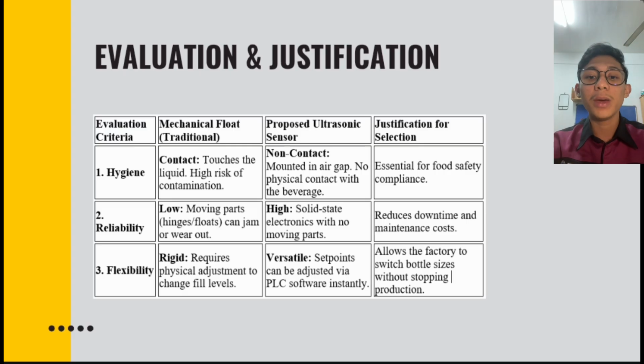Then, the feedback stage, which is our new improvement. The ultrasonic sensor continuously measures the liquid level and sends continuous feedback to the PLC, and then the PLC compares the actual level with the target height, which is the set point. Finally, the output stage. When the actual level matches the target height, the PLC closes the solenoid valve and restarts the conveyor to move the bottle to the capping station. Overall, this closed-loop system improves accuracy, reduces wastage, and increases automation efficiency. That's all from me. Thank you.